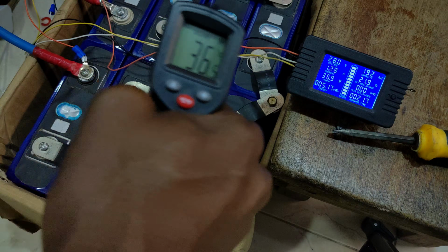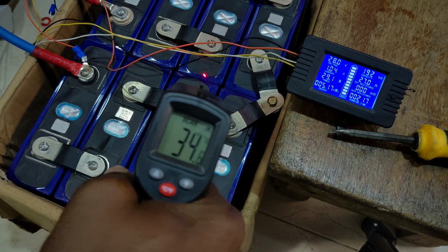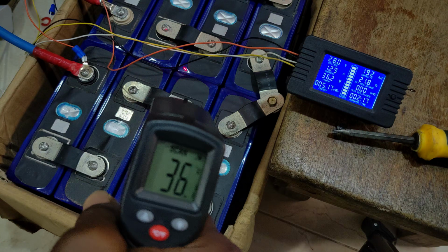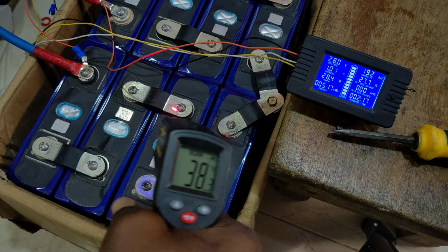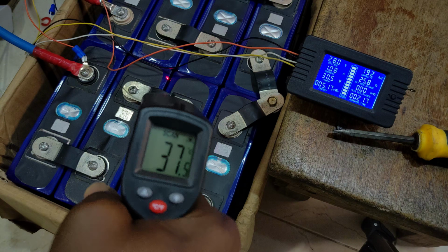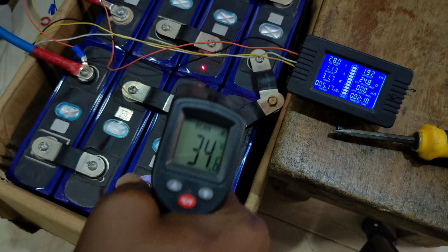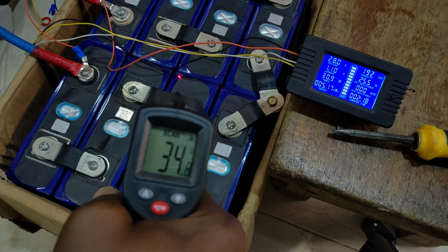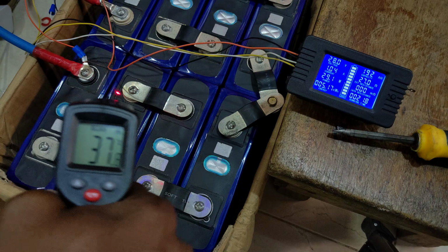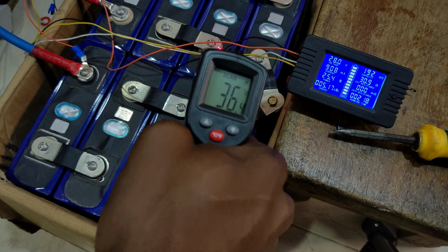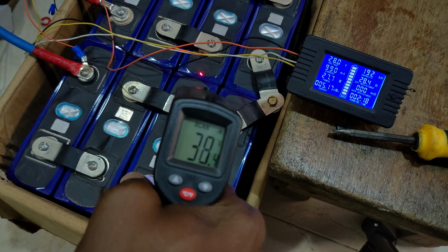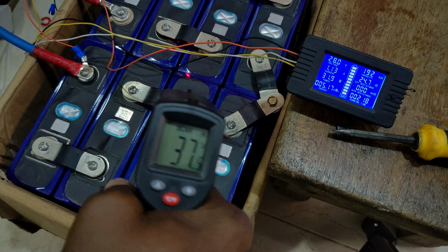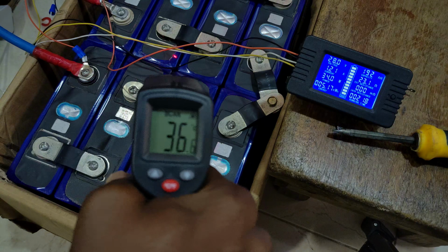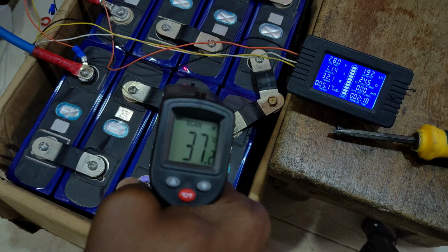Normally I don't do 100 amp charges into these batteries. I've been using 40 amps to charge, with a target voltage of 28 volts as you can see on the meter. I don't charge beyond 28 volts, which has always been my recommendation. So I do 0.2C most of the time, 40 amps charging at 28 volts, or 3.5 volts per cell.